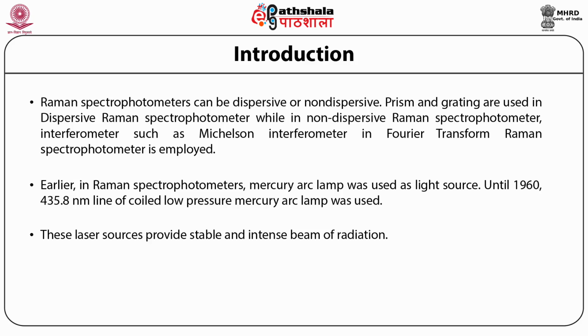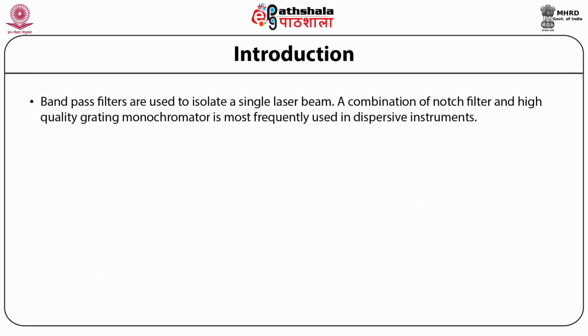Short wavelength sources such as argon ion and krypton ion lasers can produce significant fluorescence and cause photodecomposition of the sample. However, long wavelength sources such as diode or neodymium Nd:YAG lasers can be operated at much higher power without causing photodecomposition of the sample and eliminate or reduce fluorescence in most cases. Band pass filters are used to isolate a single laser beam.